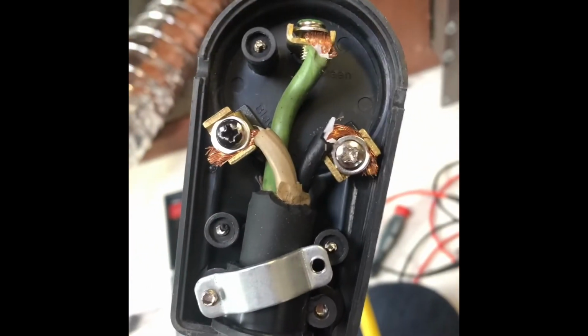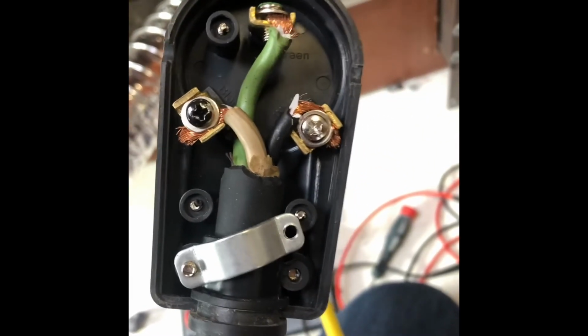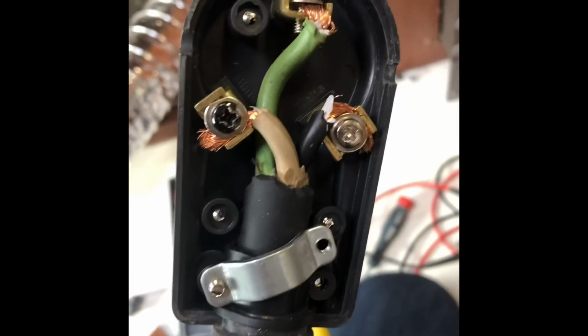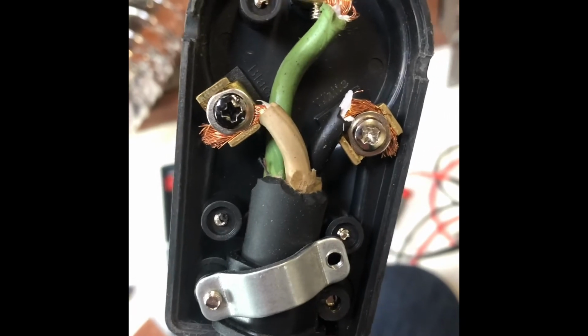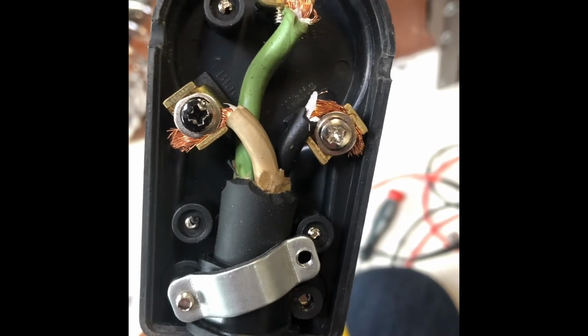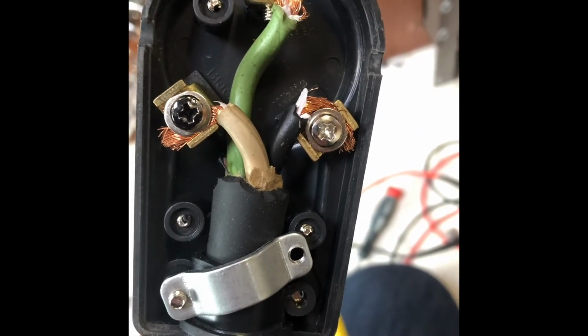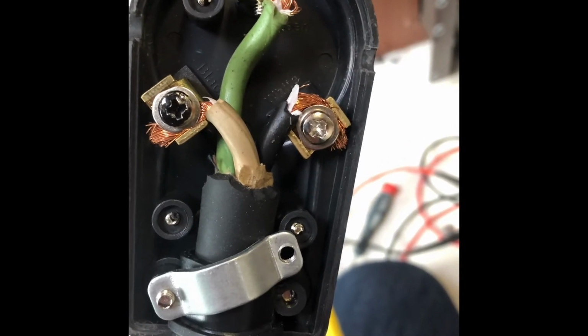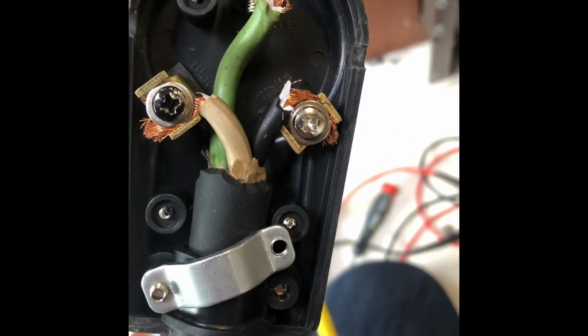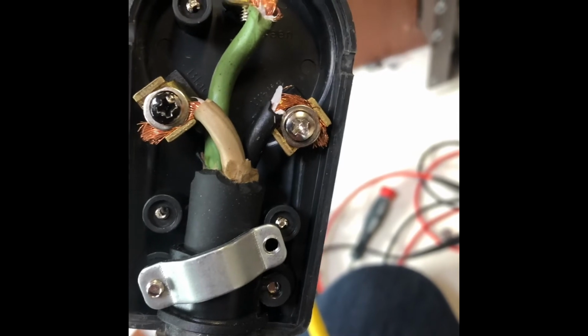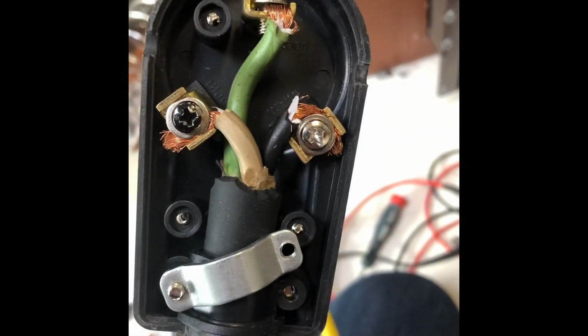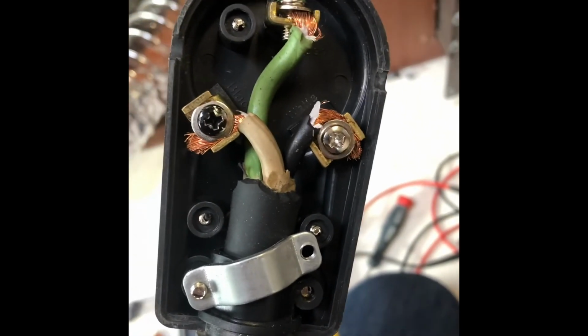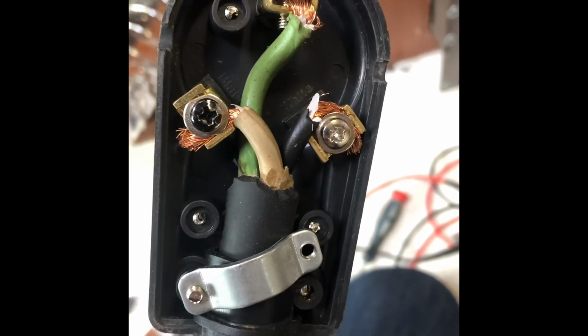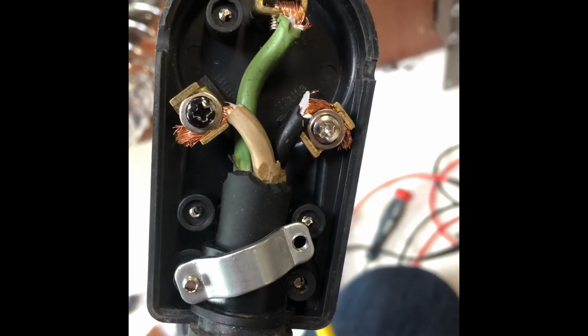Like I said, it's just a common thing to have happen. Somebody's put a replacement plug on here and not paid any attention to what's going on, and it leads to a dangerous situation - it's not just one receptacle, it's every receptacle in this motorhome that'll be coming up as reverse polarity. So just something to keep an eye out for.